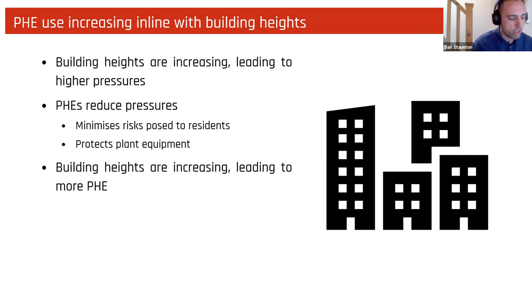So, as an industry, we're seeing an increasing need for plate heat exchangers. Building heights are increasing, leading to higher pressures on networks. Plate heat exchangers reduce those pressures, minimising risk to residents and protecting plant equipment. As building heights have generally been increasing over the last 5 to 10 years, and continue to do so, we're seeing an increased need for plate heat exchangers. Next slide.